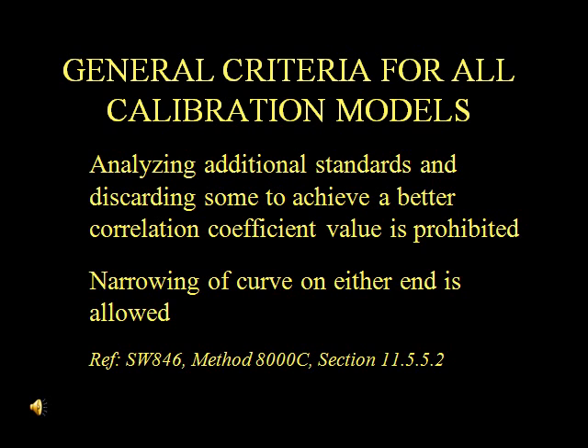However, narrowing of the calibration curve on either end is allowed. For example, discarding the highest calibration standard. If the calibration range is shortened by dropping the highest or lowest point, analytical measurements must be in the shortened range.